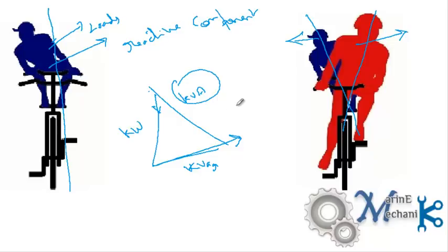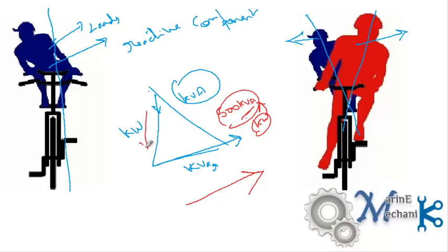To be more specific, with a generator of limited capacity, let's say 500 KVA, we usually call on board ship with the kilowatt, but we have to refer to KVA. With 500 KVA, when the KVAr increases, the kilowatt has to drop down to keep safe operating limits. So when a load leans out, the generator has to lean opposite just to maintain the balance. So this is the reactive component.